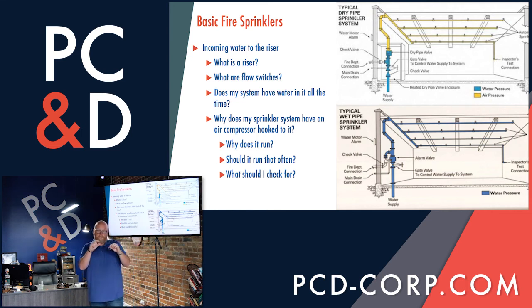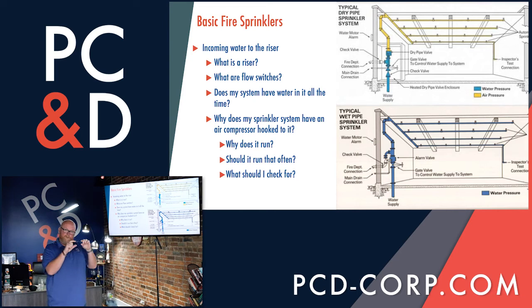These heads have certain temperature ratings and different functions of how they release the pressure behind them to let whatever is behind them go. Some of them are as low as 150, some, depending on the use and the location, maybe upwards to 180 degrees, I think. On average, as a general rule of thumb, in our nursing home setting they're typically set to trip at 160-ish, 155 degrees. You may ask, well, how does that happen? We'll talk about the heads a little bit later in the next slide. But right now, I just want to focus on the difference between wet and dry.